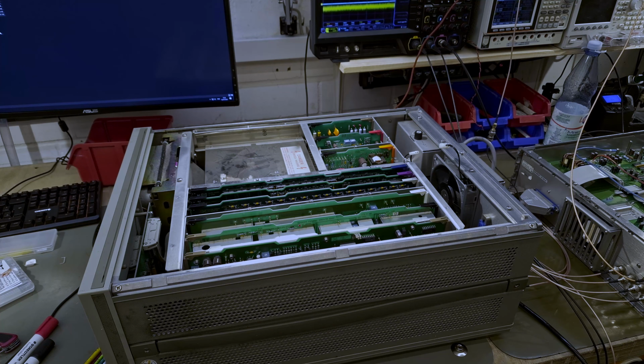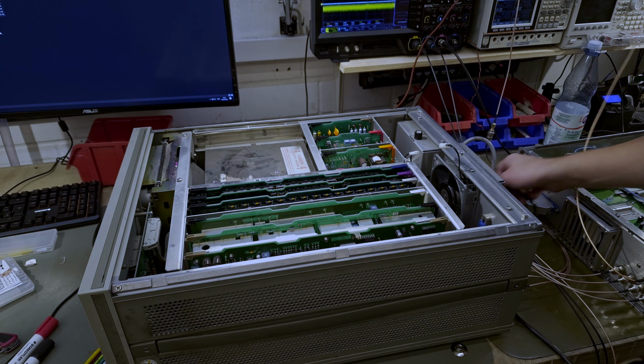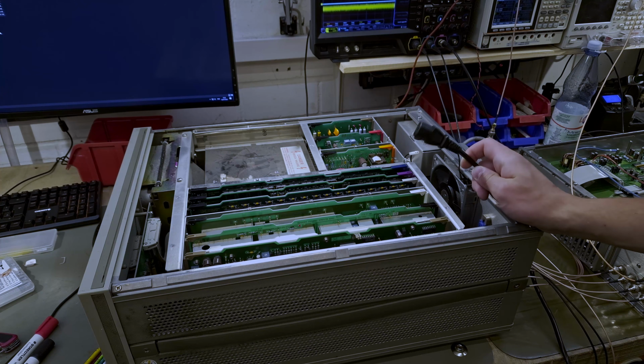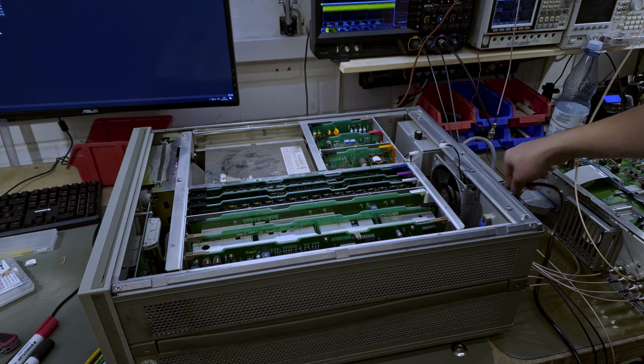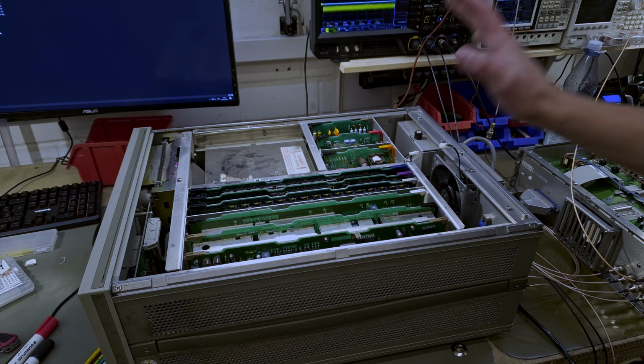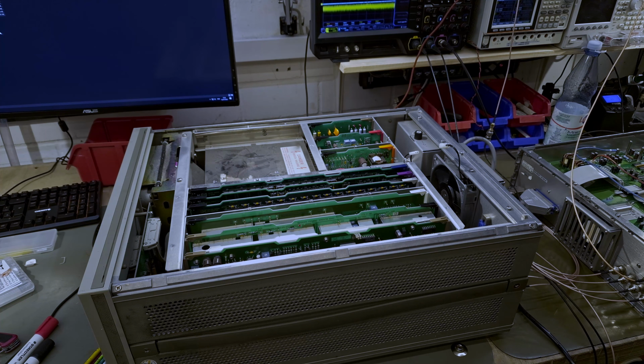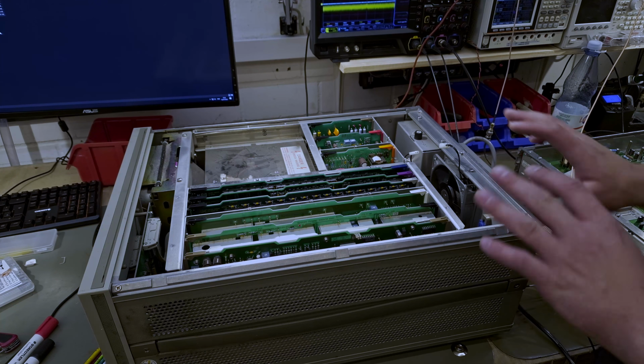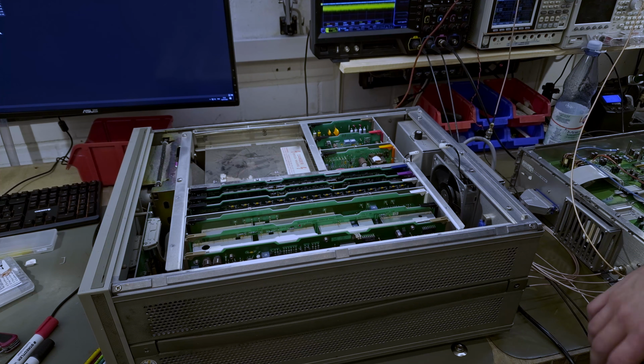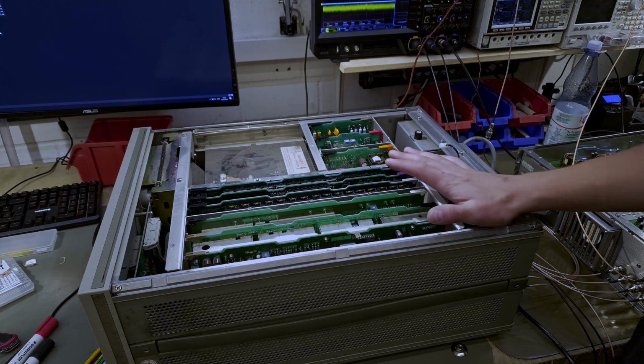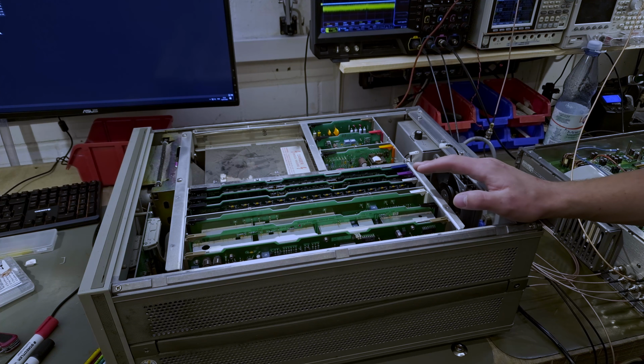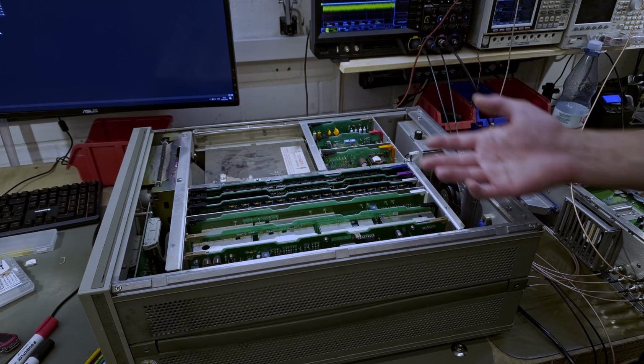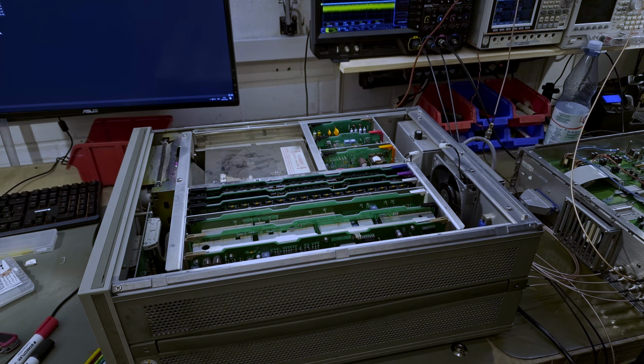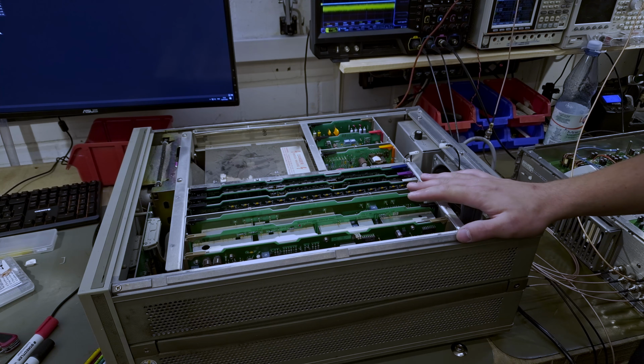So let's first of all have a very brief look at the digital control section. One thing to keep in mind: you do want to unplug things, obviously, but you definitely want to unplug and not just switch the instrument off, even if it has a real clunky power switch. Okay, that was a very bad accent. Because, especially with RF gear, there's always the possibility that there are going to be some standby voltages, for example, for oscillators, frequency reference oscillators. They do like to be kept warm.